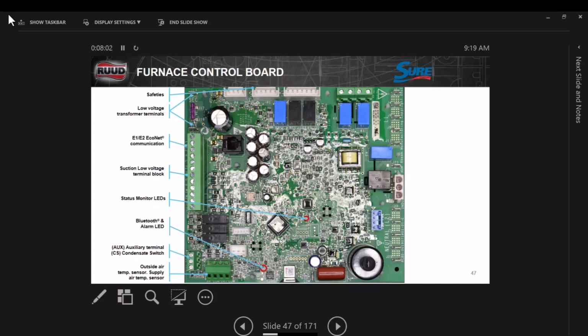We have to take our switches to the auxiliary port. The CS means condensate switch. You're going to hook it up there. On the bottom is a common, so it would go here and here. And then we have an auxiliary that could be used as a secondary pan switch or whatever you have. You can put that there. Right below that is where the outside air sensor goes.